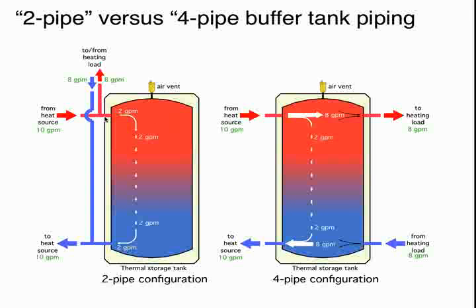And just to show you a comparison, let's start over here with the two-pipe configuration on the left. We've got 10 gallons per minute of flow coming in from our heat source. Let's say our load requires 8 gallons per minute. Well, that leaves 2 gallons per minute to flow over into the tank and ultimately would flow downward through the tank and back out here. It recombined with the 8 gallons per minute returning from the load, and 10 GPM would go back to the heat source.